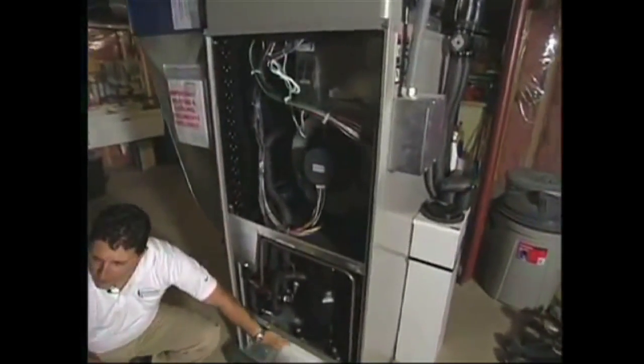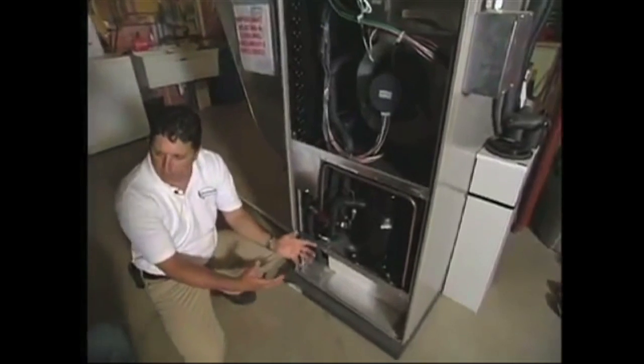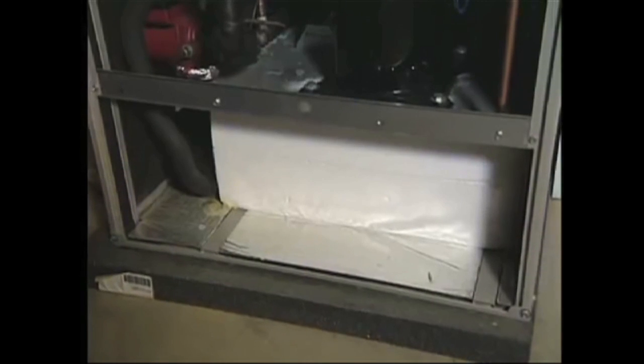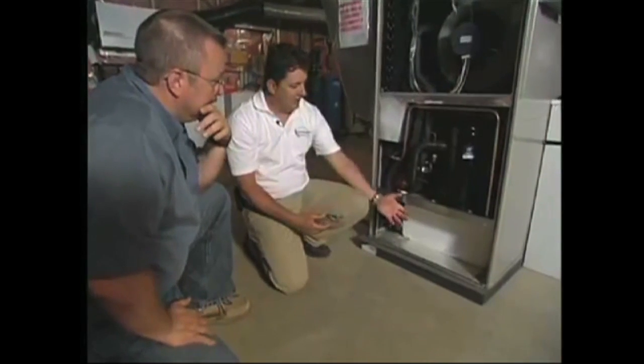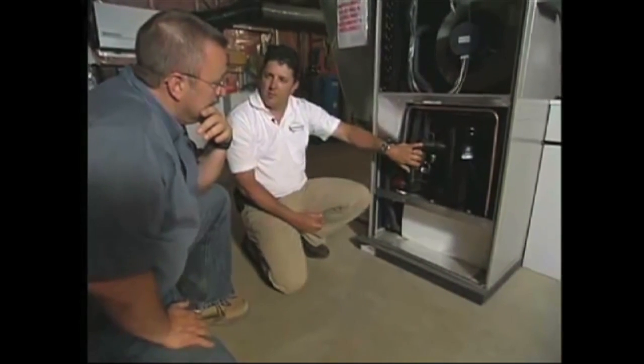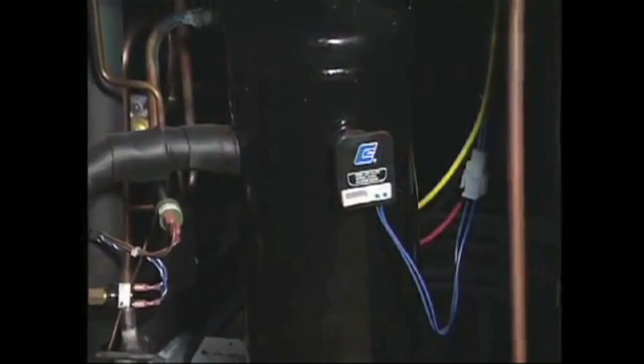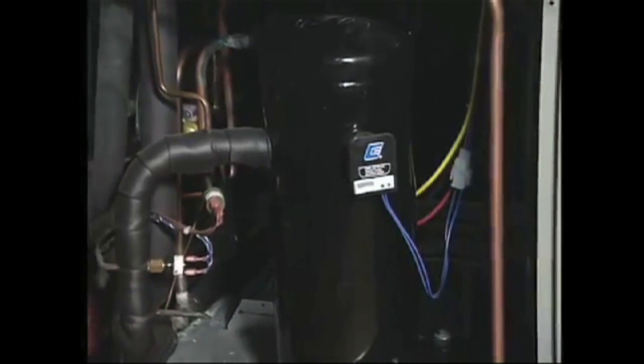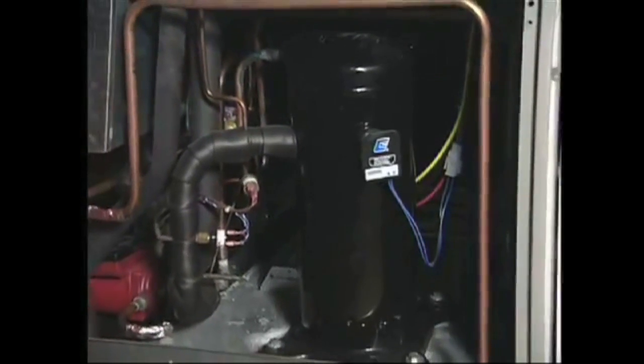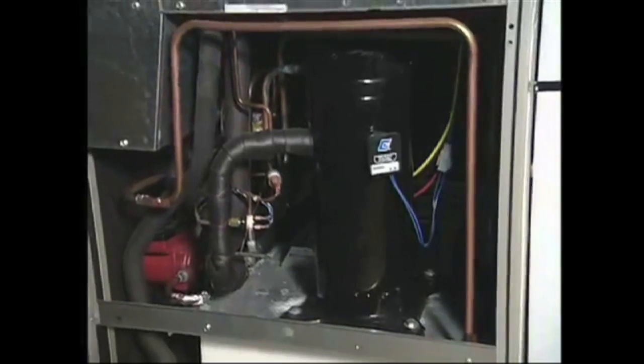So the water-to-refrigerant heat exchanger in heating mode is absorbing heat energy from that fluid that's being circulated from the ground, usually about 50 degrees, as we mentioned. Yeah, 50 degrees all the way through down to 30 throughout the wintertime as we remove heat from the ground. And that energy then gets absorbed into the refrigeration system, that's part of the compressor. So through that heat exchange process, we absorb the energy. The compressor then intensifies that energy through heat of compression. Of course, that's electric driven.